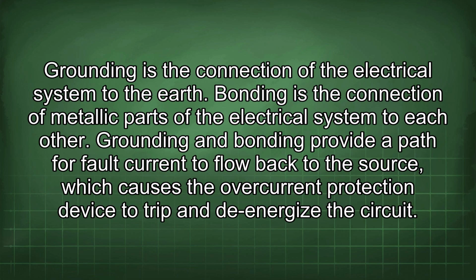Grounding is the connection of the electrical system to the earth. Bonding is the connection of metallic parts of the electrical system to each other. Grounding and bonding provide a path for fault current to flow back to the source, which causes the overcurrent protection device to trip and de-energize the circuit.